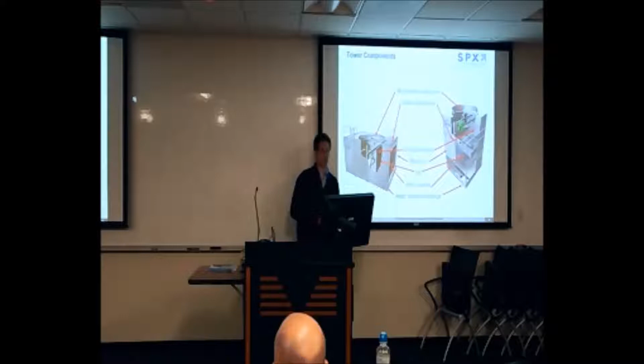You can see the buildup in the hot water basin, not mold, but how much debris is building up in there. You come back the next week and notice there's a lot more. Okay, maybe we have a problem with our chemical treatment, or maybe our sweeper system's not working correctly. So it's good to be out there regularly, even if you're not doing technical work, just to see what your cooling tower is doing.